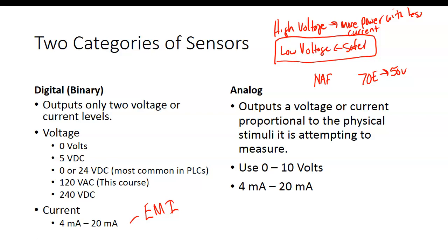The problem is that voltage circuits use low current but high resistance. If a magnetic wave passes through a high resistance conductor, it induces a voltage, which can cause problems. It's almost impossible for EMI to generate a current, because we don't have enough turns of wire for all that to add up. So current signals are almost impervious to electromagnetic interference.